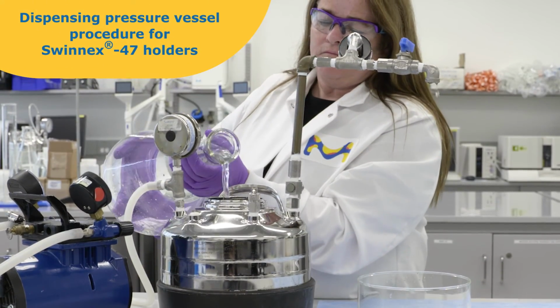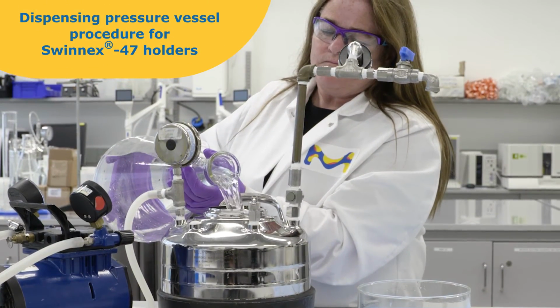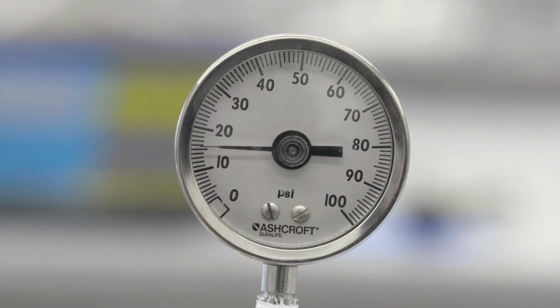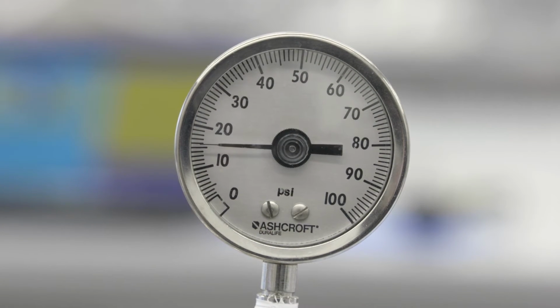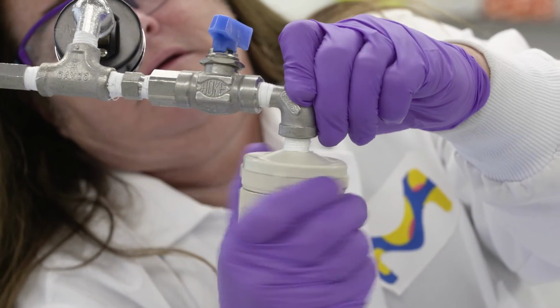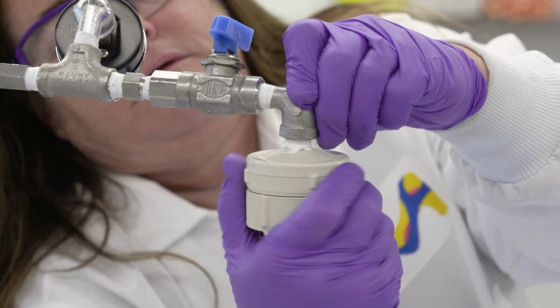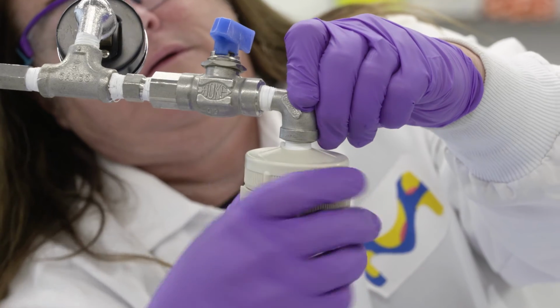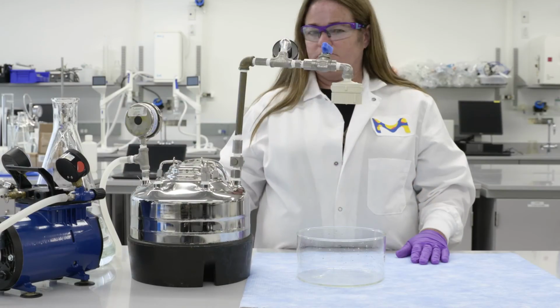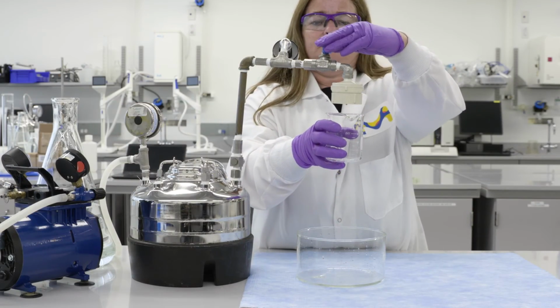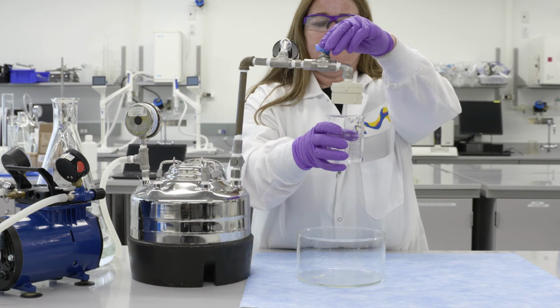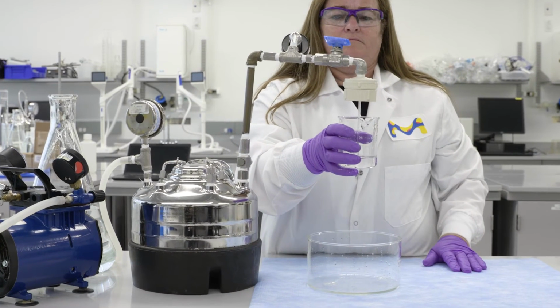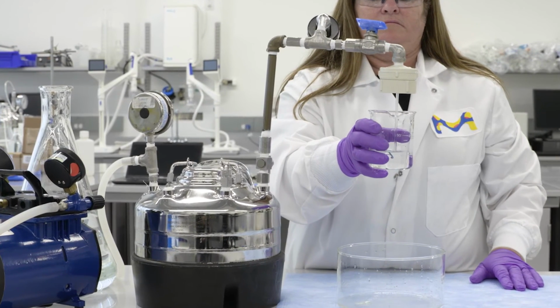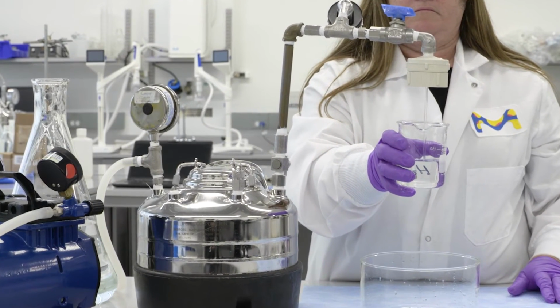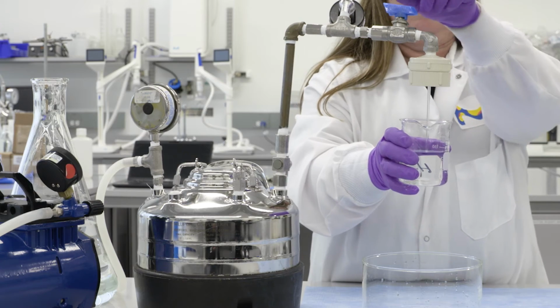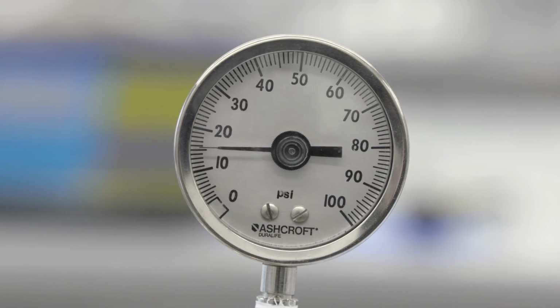When using the 47mm Swinnex filter holder with dispensing pressure vessels, note the maximum pressure rating for system requirements. Check the inlet and outlet connection compatibility to the Swinnex holder to the inline pressurized dispensing system. Do not exceed maximum device pressure rating of 5.2 bar or 75 psi for the Swinnex 47 holders. In this example today, I will be showing you the filtration method using a 5-liter dispensing vessel pressurized with a positive pressure pump set to 15 psi.